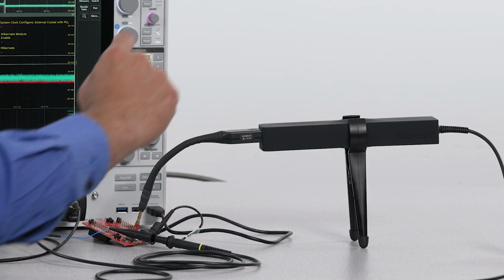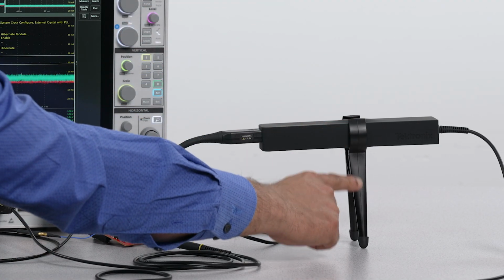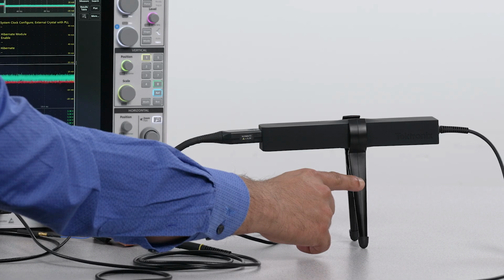The TCP current probe is also a great choice for measurements on low power mobile and IoT devices. Some power rails are moving to 48 volts and traditional differential probes don't have the common mode voltage rating for these applications. This time, we are using a handy bipod which is included in the standard package.